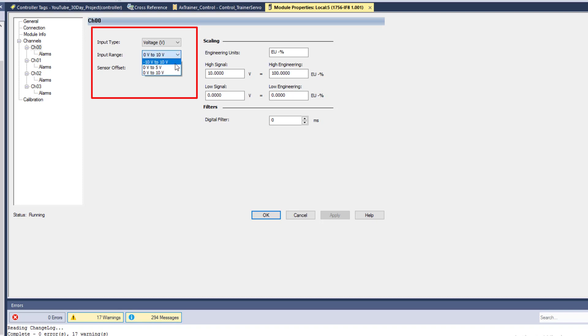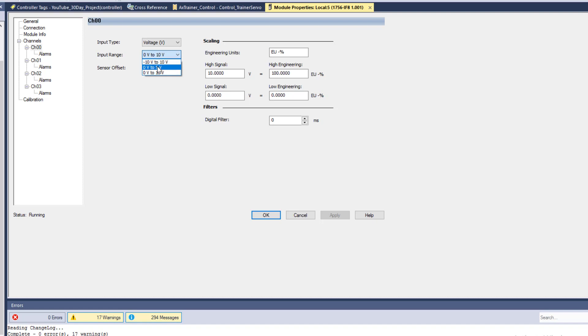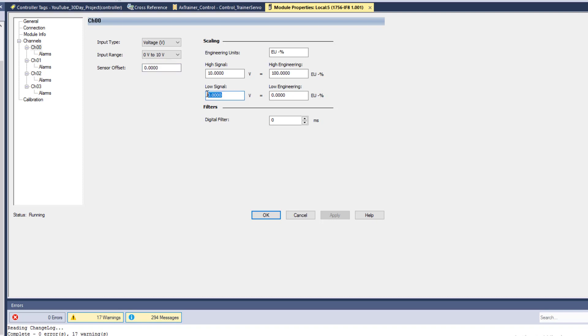This is where you change your input scaling. Whatever device you're using could be using negative 10 to positive 10 volts, zero to five volts, or like a potentiometer using zero to 10 volts. I'm going to talk about zero to 10 volts — that's the easiest to scale. I'm not going to change anything on the sensor offset because that will generally affect the end result of your zero point.